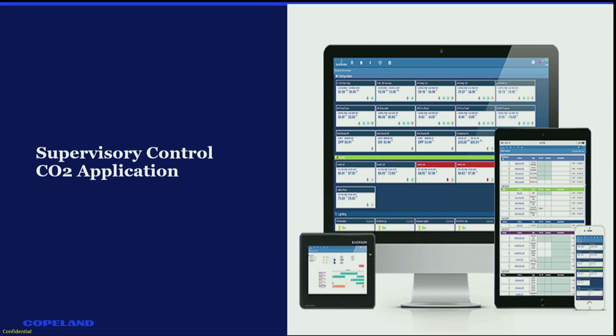So we've got the multiplex board, which is our I/O. It talks I/O net, so you'll need a communication port dedicated for the I/O net. You've got the iPro high pressure valve controller and the XM case controllers, 678, 679s, which talk Modbus. You've got the CC200, that's a newer case controller that we've got. It can talk Modbus or BACnet. And then you've got leak detection, so we've got the MRLDSs. We also have some RLDSs. I'll show you all of our leak detection. Those talk Modbus. And then you've got the EVM, the EVH variable speed drives, which talk Modbus or BACnet.